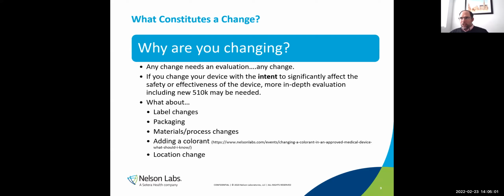Because any change that you go through needs an evaluation. And I mean any change, because we need to see if a change is going to impact the patient. And so we're talking about a change in your packaging, even your packaging configuration might have an impact that we have to look at. We've seen it happen. Sterilization changes could be huge.